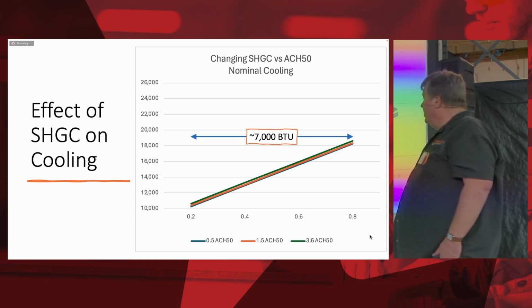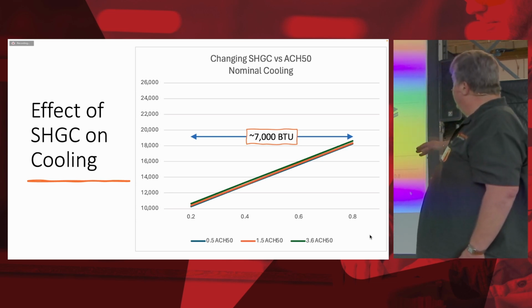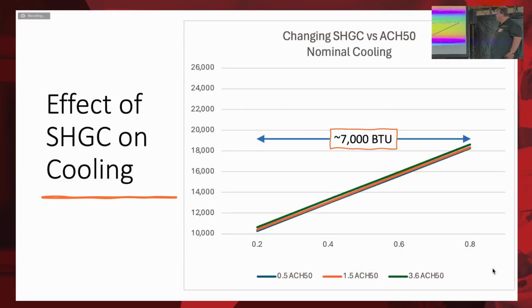But a lot of these relationships, when you get down to them, it turns out there's a hell of a lot of BTU on the table just by ranging your solar heat gain coefficient from 0.2 to 0.8 - 7,000 BTU on that house, which is only 12,000 BTU. Makes a lot of sense. Take a look.